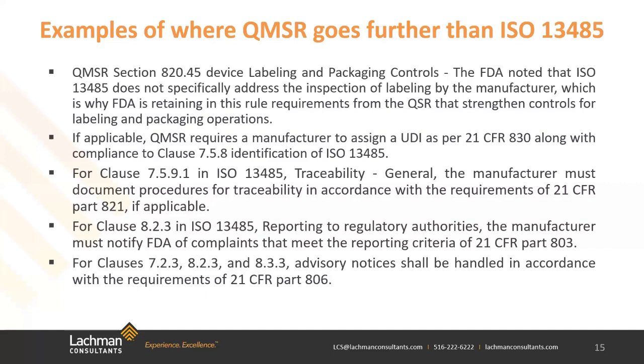Next, we'll talk about UDI. Where QMSR requires a manufacturer to assign a UDI, the manufacturer must document the system to assign unique device identification to the medical device in accordance with the requirements of 21 CFR Part 830, which is unique device identification, along with the clause from ISO 13485, 7.5.8. Next bullet is traceability.